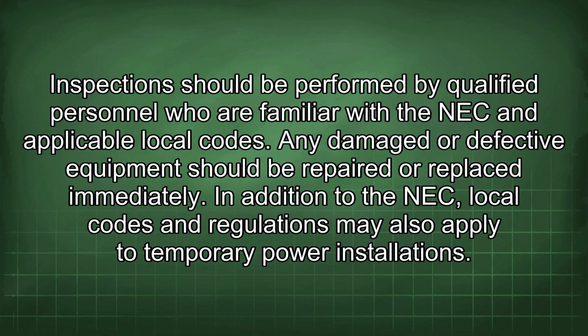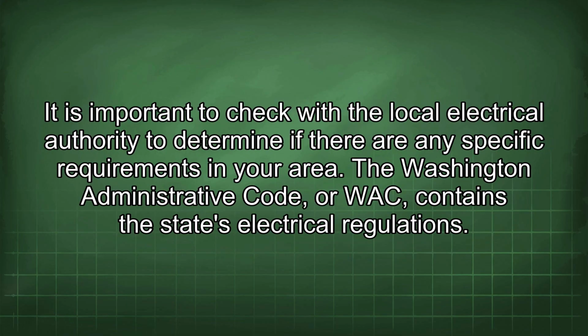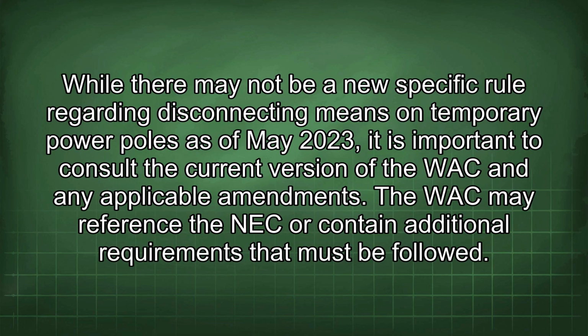In addition to the NEC, local codes and regulations may also apply to temporary power installations. It is important to check with the local electrical authority to determine if there are any specific requirements in your area. The Washington Administrative Code, or WAC, contains the state's electrical regulations. While there may not be a new specific rule regarding disconnecting means on temporary power poles as of May 2023, it is important to consult the current version of the WAC and any applicable amendments. The WAC may reference the NEC or contain additional requirements that must be followed.